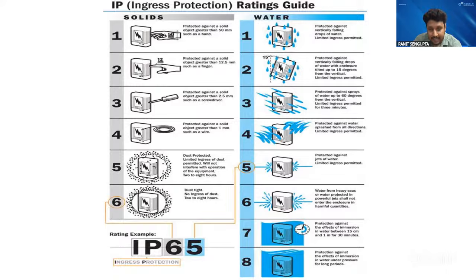Rating 8 means it's at 1 meter depth but for more than 1 hour. That's how we implement the IP test, and it's very important for battery packs. You know about weather conditions - so minimum IP67, or ideally IP68, should be required for battery packs, because hazards can happen if there's a short circuit inside.